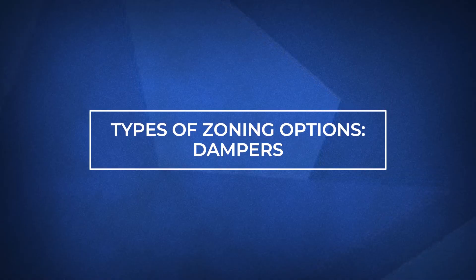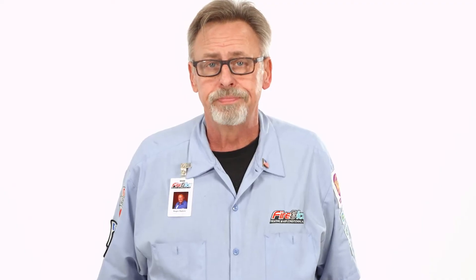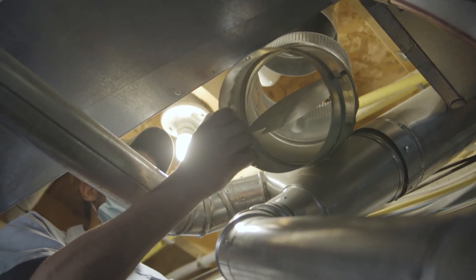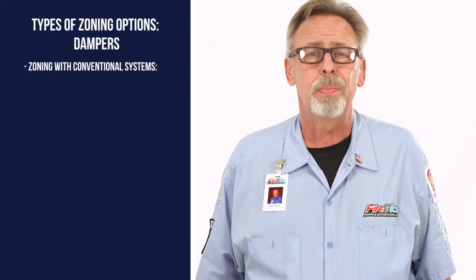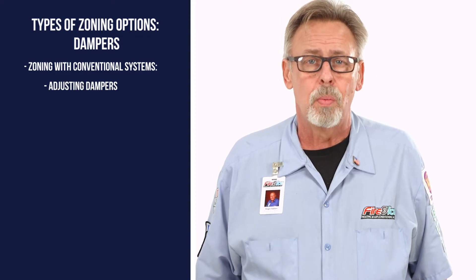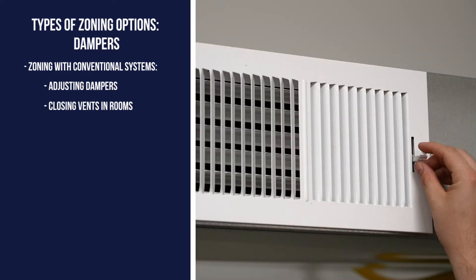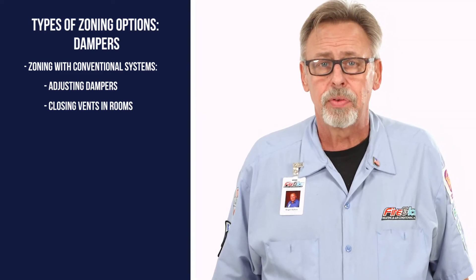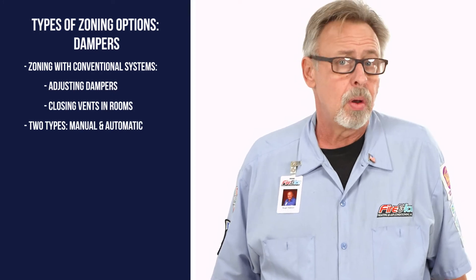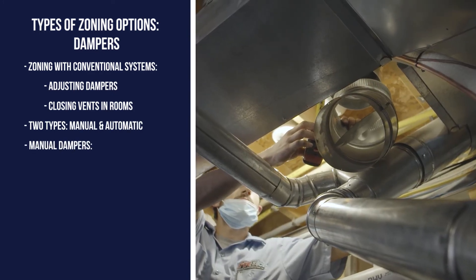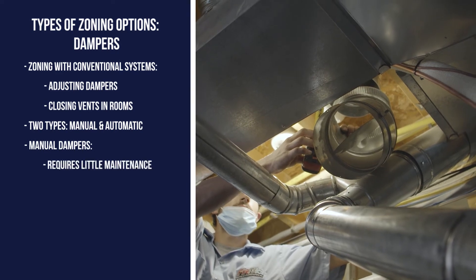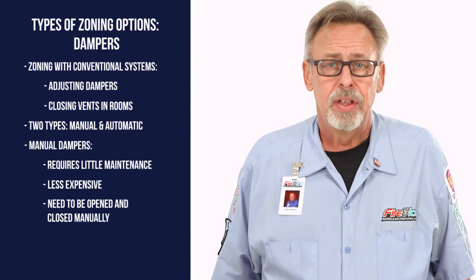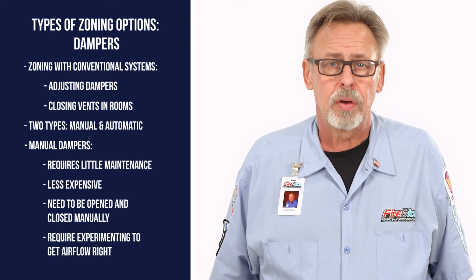Remember the conventional heating and cooling system described earlier? If dampers were included on that system, we could eliminate the uneven temperatures. Adjusting dampers in the ductwork is one of the cheapest ways to create zones in a home. Additionally, closing off vents in rooms that aren't used is another way to zone. If your home's ductwork lacks dampers, they can be added. There are two types: manual and automatic. The benefits of manual dampers are that they need very little maintenance and are less expensive. The downside is they have to be opened and closed manually, and you'll likely need to experiment to get airflow where you want it.